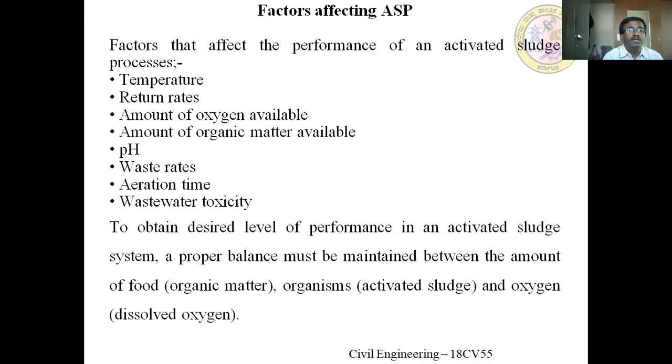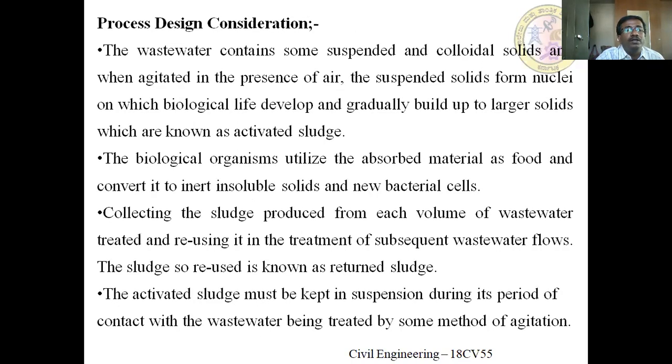It depends upon the type of the effluent and the nature of the industries. To obtain the desired level of performance in an activated sludge system, a proper balance must be maintained between the amount of food, which is mainly called the food to microbial ratio, the organisms in the activated sludge, and oxygen. That is, the amount of oxygen required for that particular system.